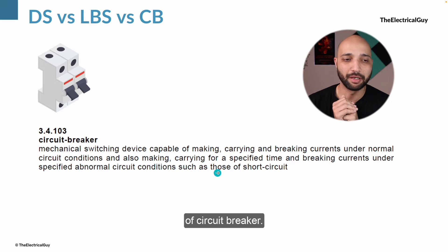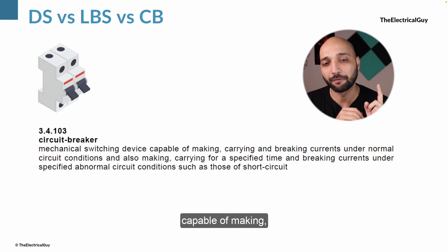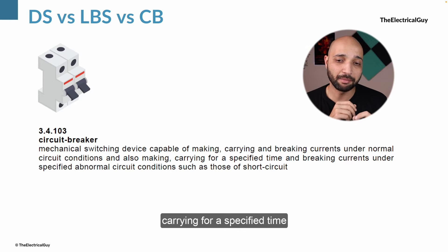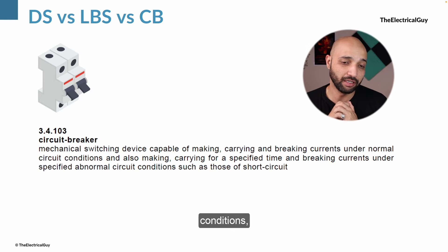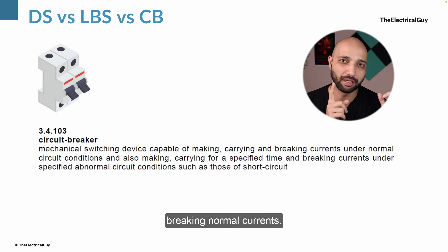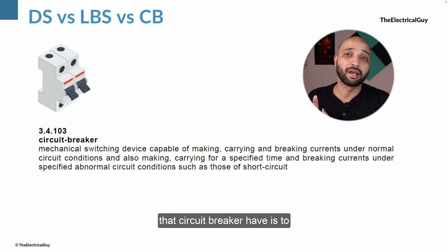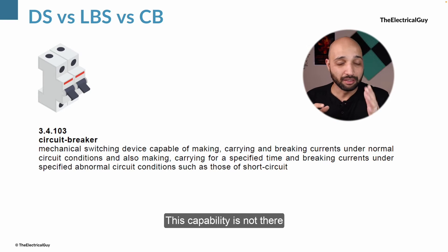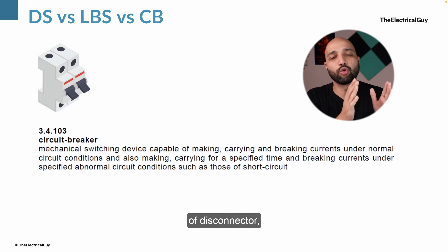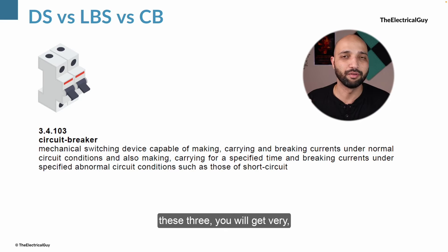Now the definition of circuit breaker per IEC: a circuit breaker is a mechanical switching device capable of making, carrying and breaking currents under normal circuit conditions, and also making, carrying for a specified time, and breaking currents under specified abnormal circuit conditions such as those of short circuit. So circuit breakers are capable of making and breaking normal currents, plus the additional capability to make and break huge fault short circuit currents — a capability not present in switch disconnectors or disconnectors.